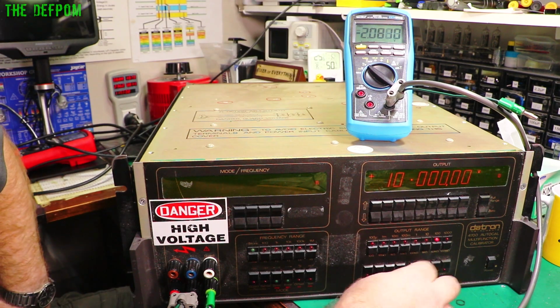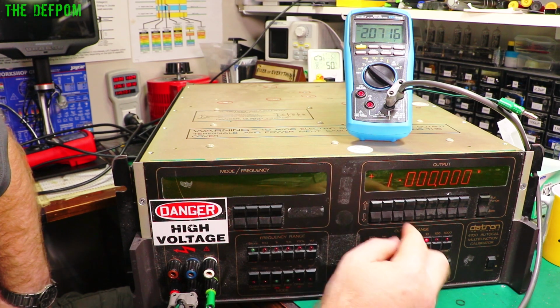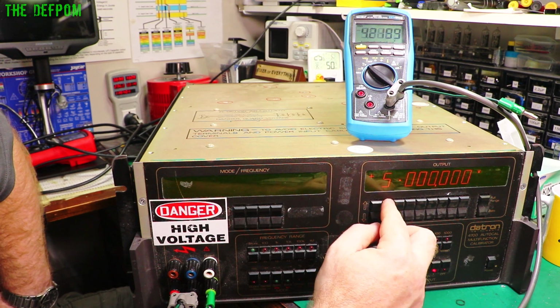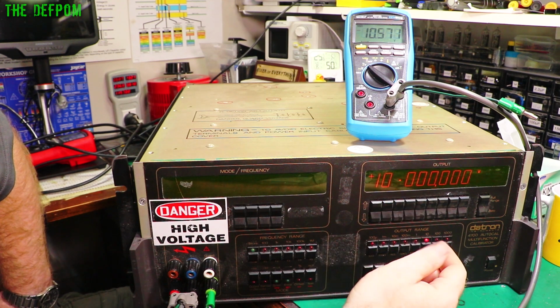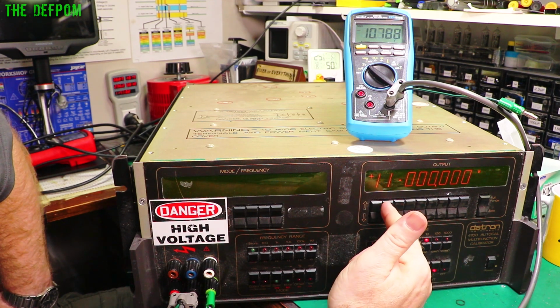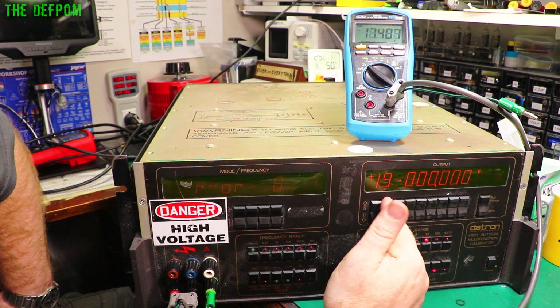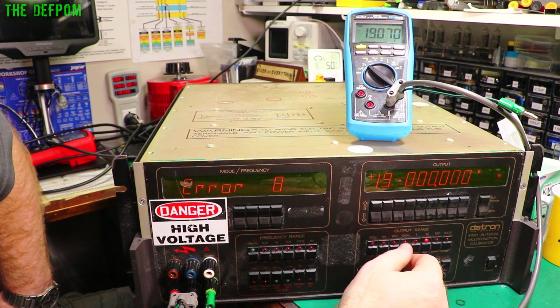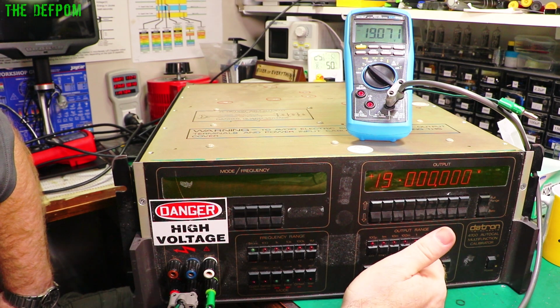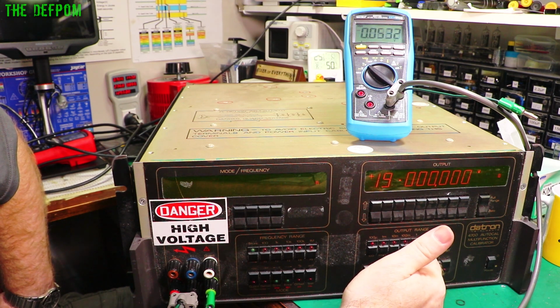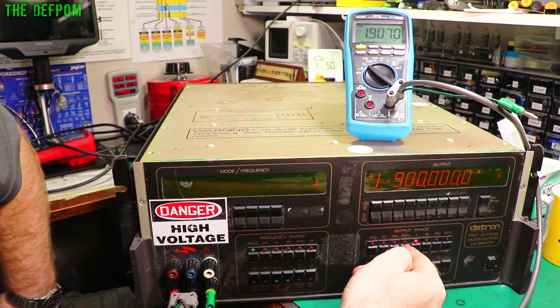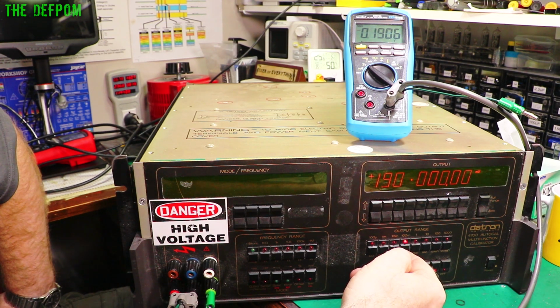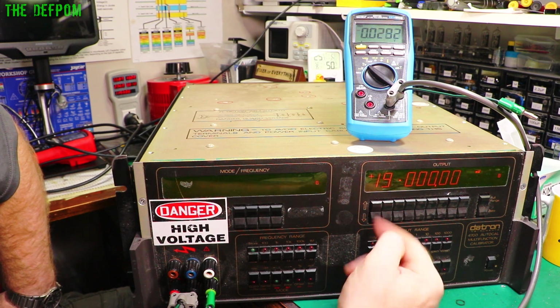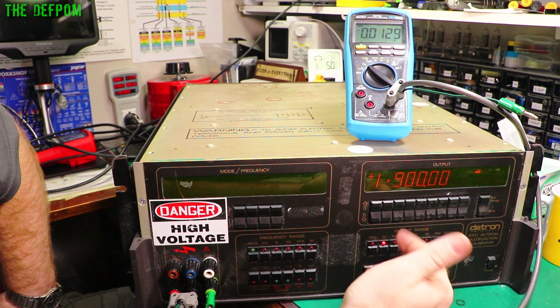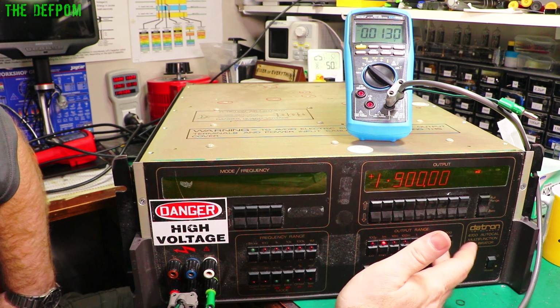See that? Back to the 10 volt range. We're getting 2 volts. So if I go up, we will get 10 volts on this range. Up to 19 until it says out of range, but that's okay. 19, that's it. So let's go back down to 1 volt. That's there. 1.9. Yep. 100 millivolts. That's there. 19 millivolts. That's out by 10. So this is interesting. 1 millivolt. It's out of range. I need a better meter for that. So okay.